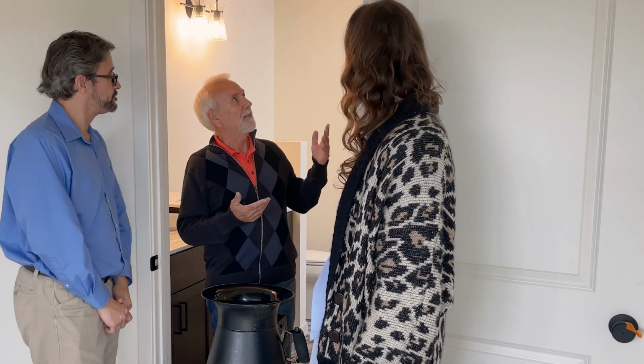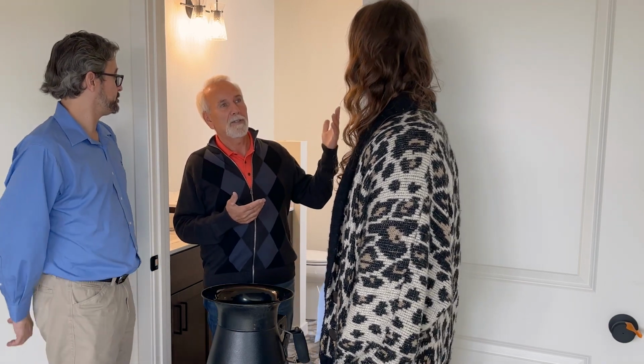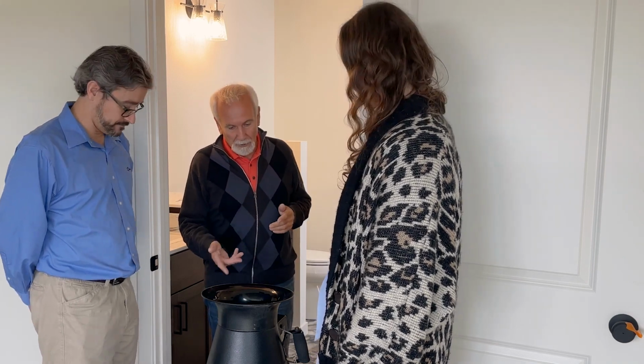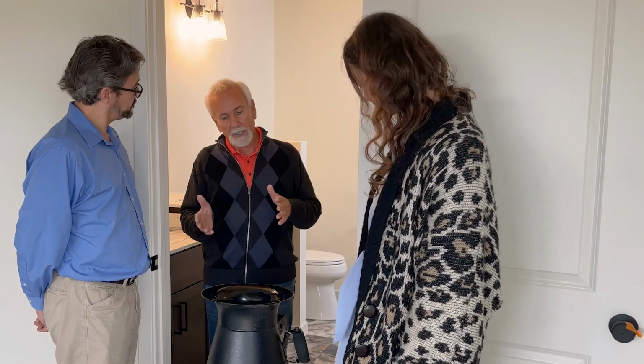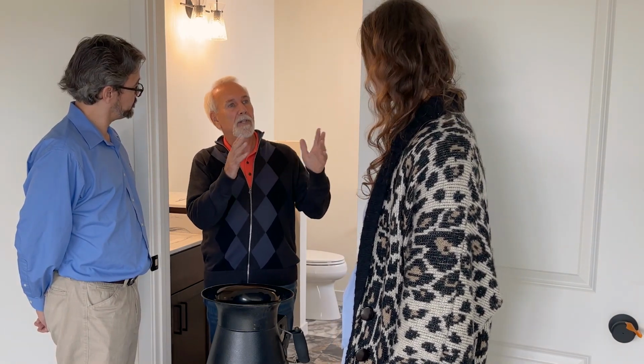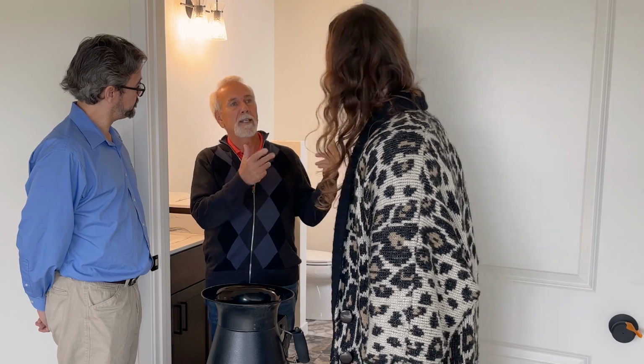And in order to verify that that can happen, we need to measure the airflow on the exhaust fan in the bathroom. So we have a digital flow hood here that we hold up. It's got a capture on it. We just simply hold it up. When the fan is running, it displays the digital value. We can look at that and then say, okay, it's 110 rated CFM, for example. What are we actually getting for airflow?